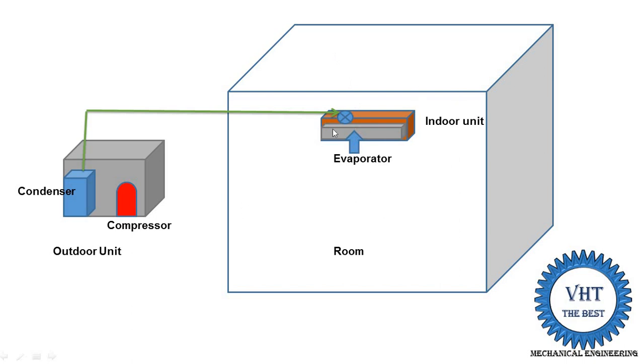The split air conditioning also performs dehumidification. Room air contains humidity, which condenses on the evaporator coil due to the dew point temperature. A tray is placed below the evaporator to collect water droplets and drain them outside. The system controls four air parameters: temperature, relative humidity, air velocity, and cleanliness. An air filter is provided at the top of the evaporator to clean the incoming air.